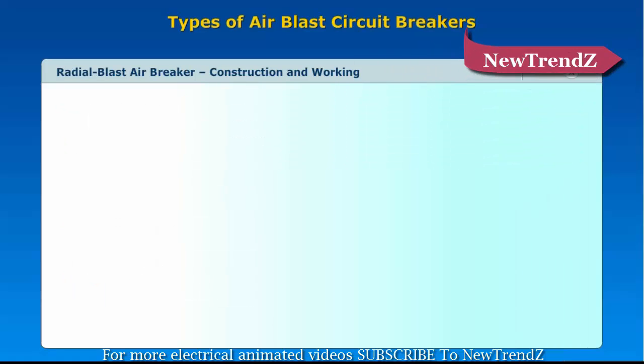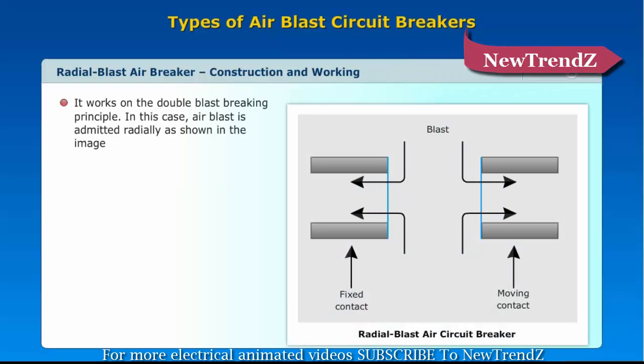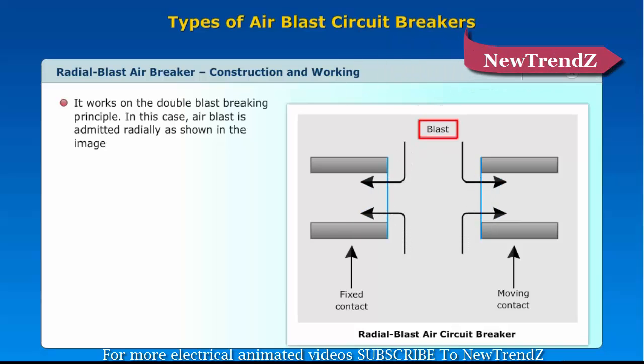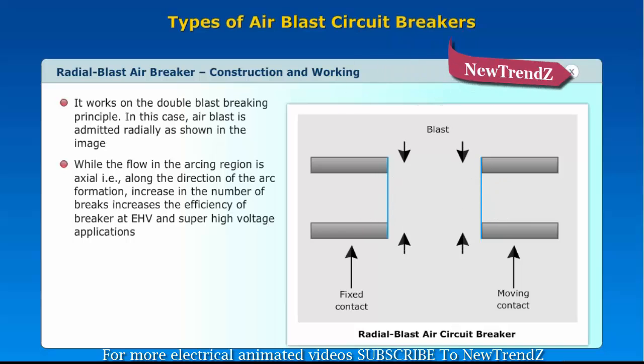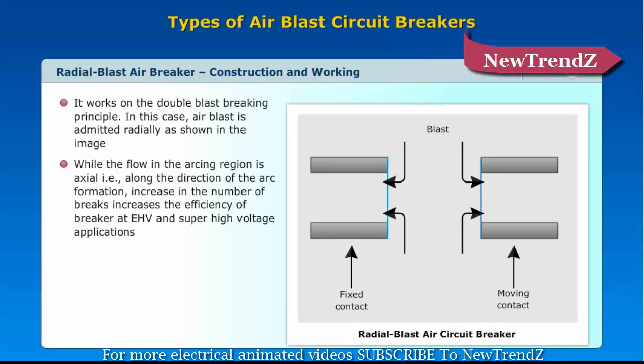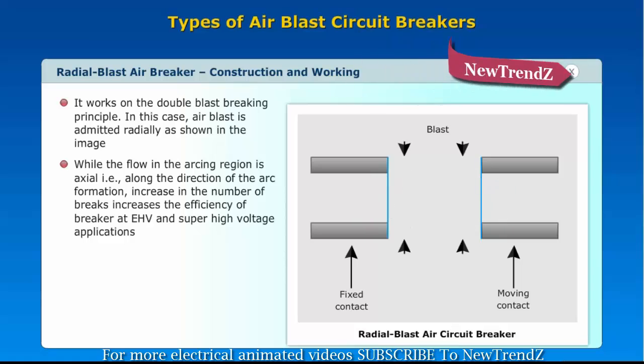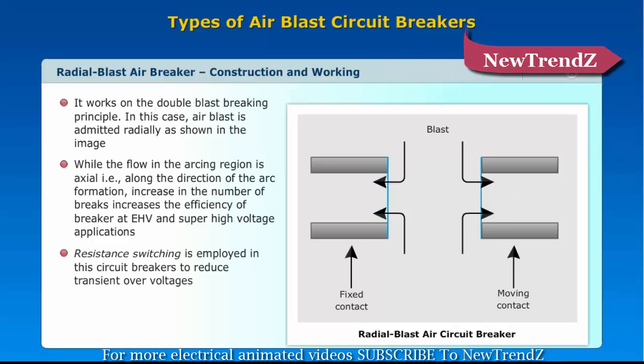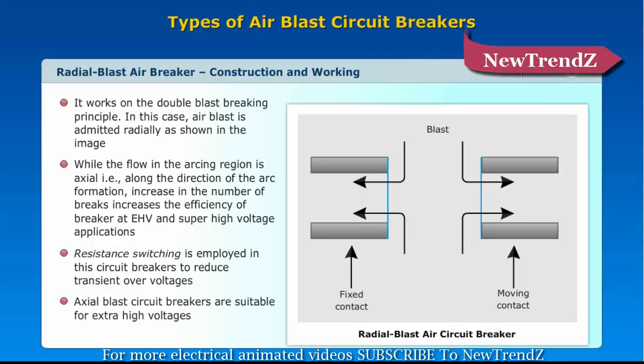The radial blast circuit breaker works on the double blast breaking principle. Air blast is admitted radially, while the flow in the arcing region is axial, that is, along the direction of arc formation. An increase in the number of breaks increases the efficiency of the breaker. At EHV and super high voltage applications, resistance switching is employed to reduce transient over-voltages. Axial blast circuit breakers are suitable for extra high voltages.